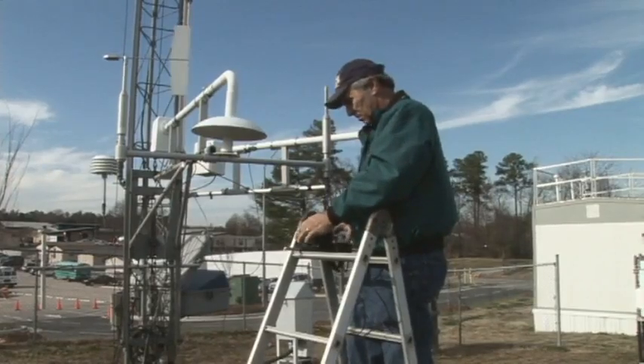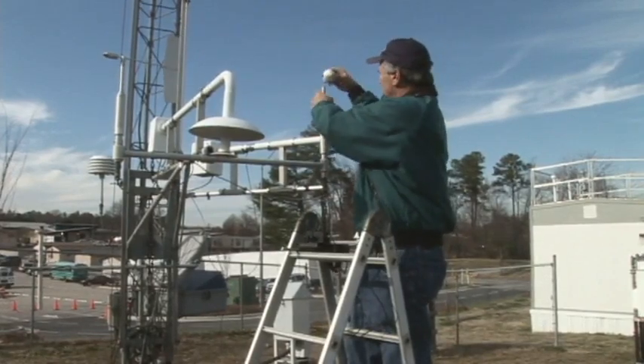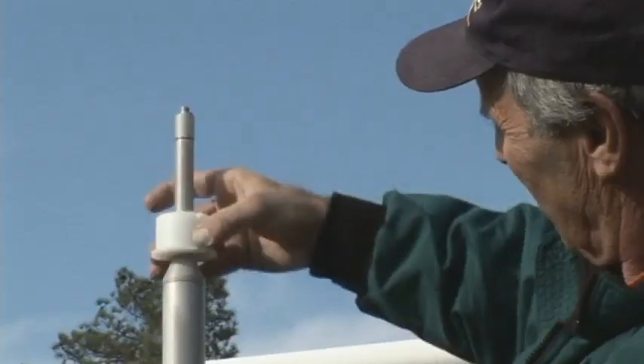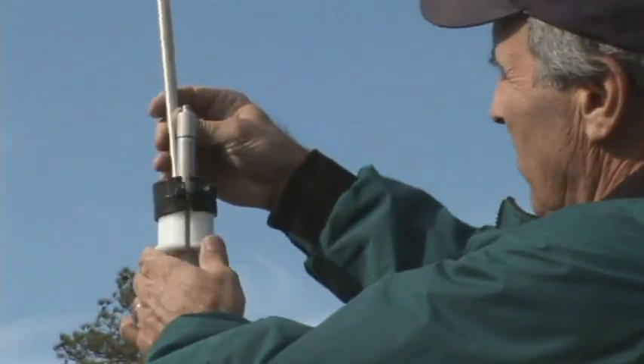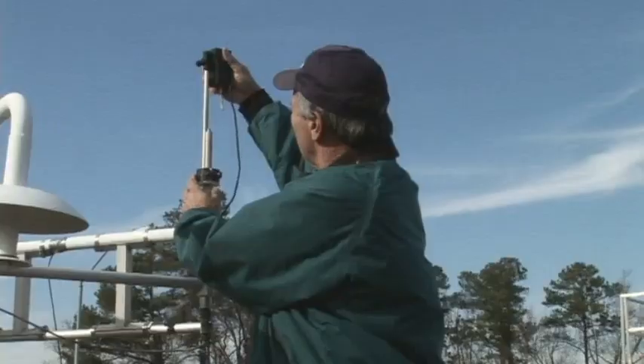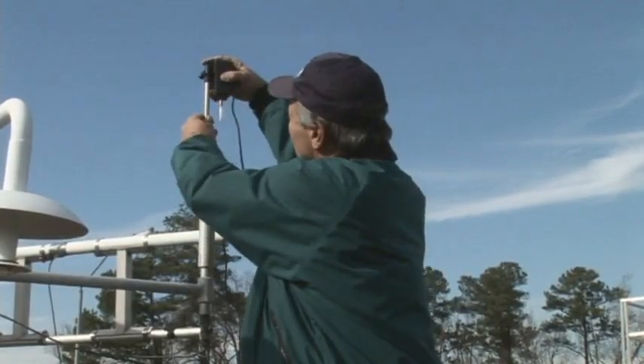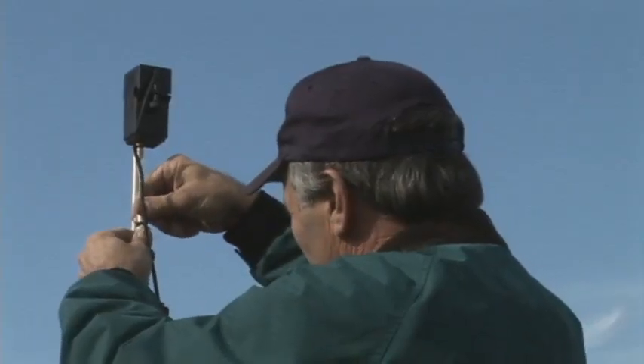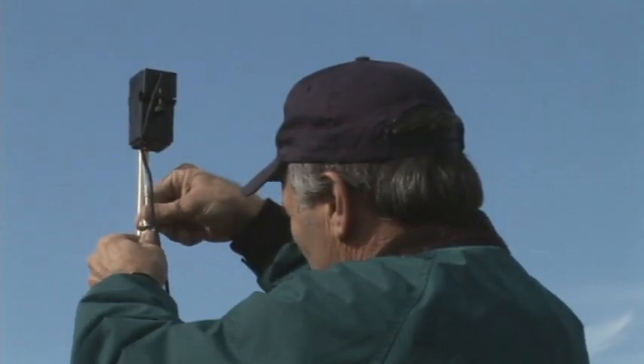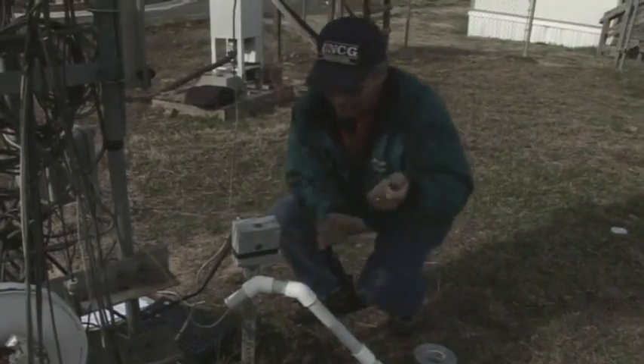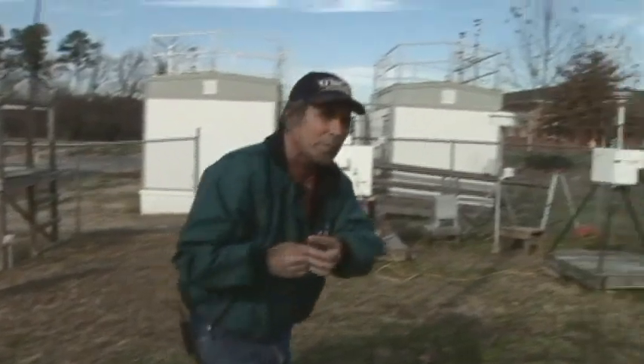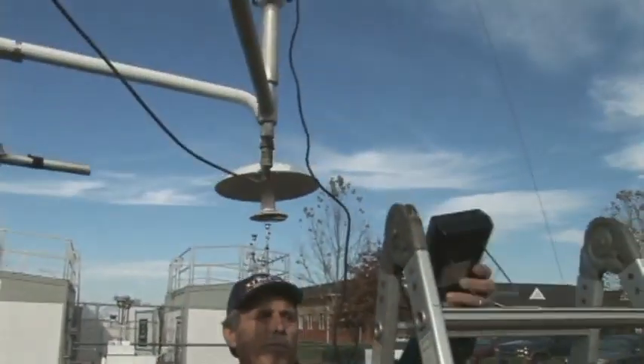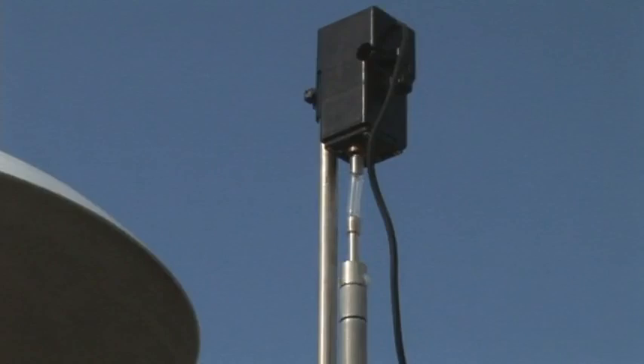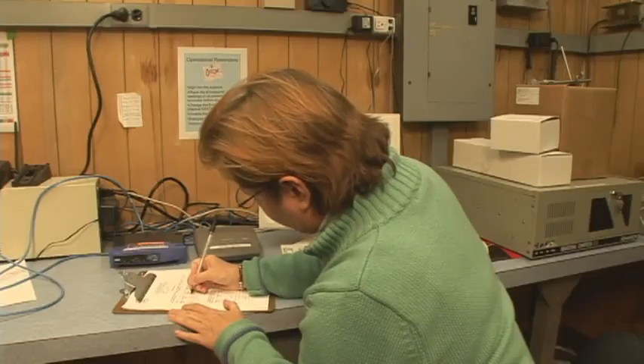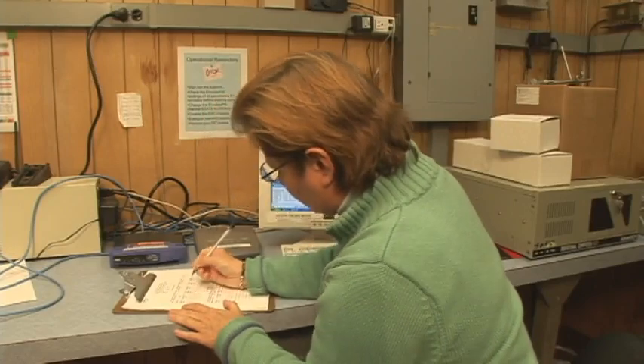The site technician is now attaching the motor shaft via the grommet or rubber tubing to the anemometer shaft. Caution should be used here. It is important that the appropriate tubing or grommet be used so that neither anemometer nor motor shaft slips. This will cause inaccurate readings. Once the rubber tubing is attached and is secure, the technician should start the motor and dial in the first value. This should be approximately 10% of the full-scale range. Once the controller shows that the speed has stabilized, the second technician should record the response of the DAS.